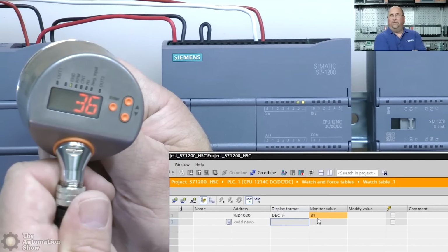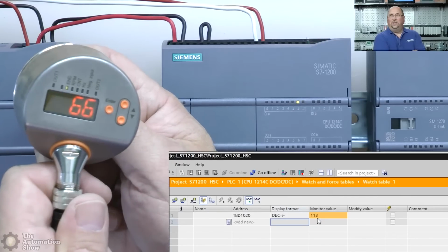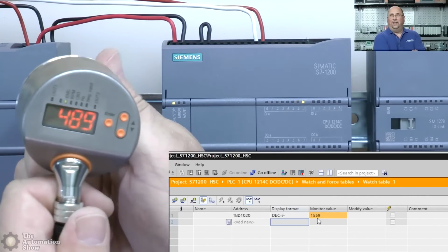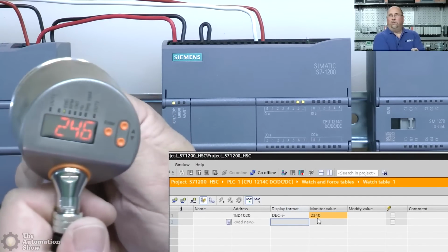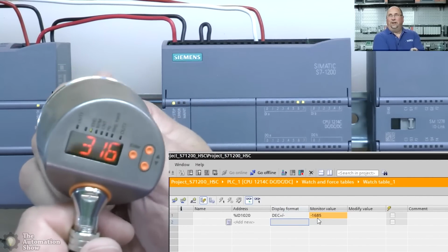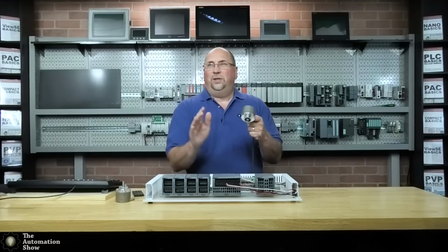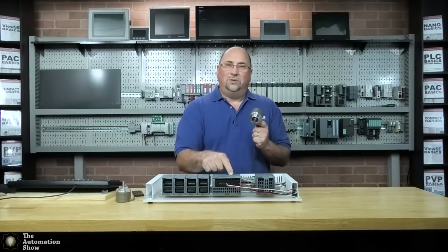And we can see the monitoring value for 1020. It's going up. I'm going to turn it fast. Yeah, look at that. I'm not missing anything, right? Okay, and I can go in the reverse direction here. And there we go.